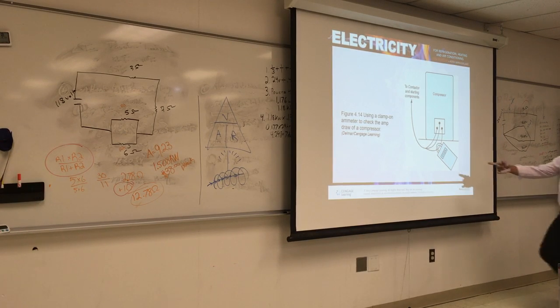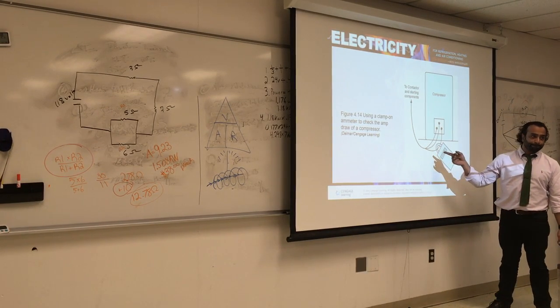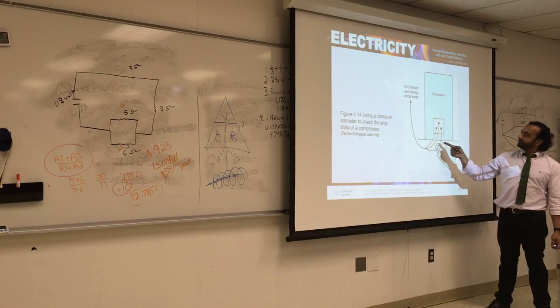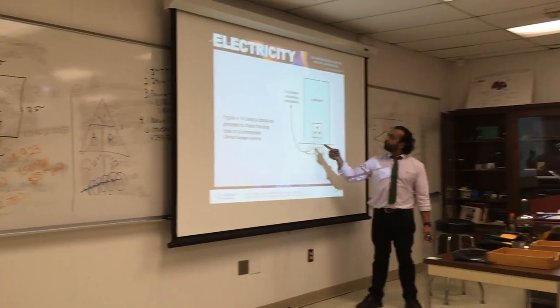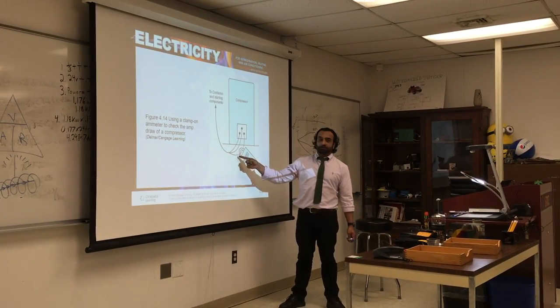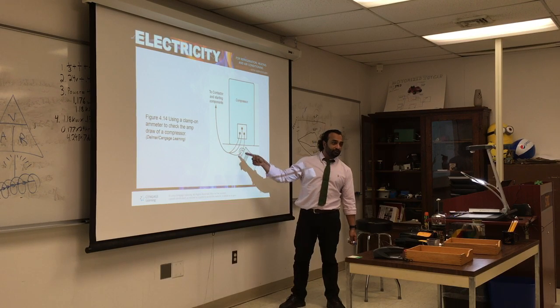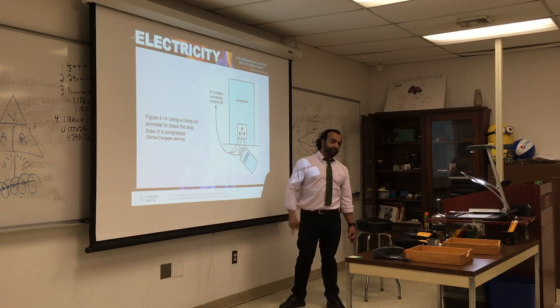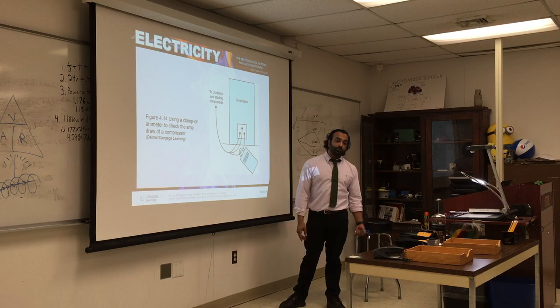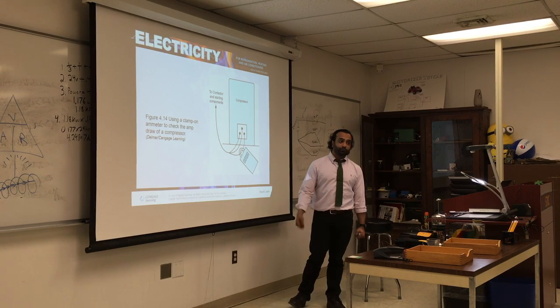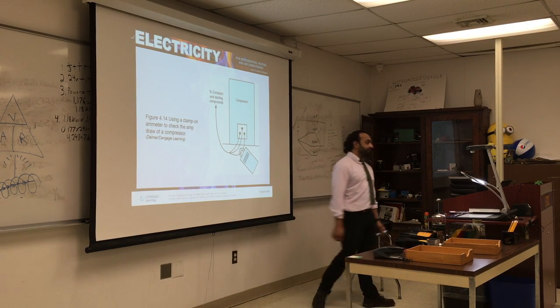So again, if we have a single-phase wire, whether you put your clamp on the hot or neutral, you get some reading. But the equipment has to be on. If you put it on when the equipment is dead or with an open circuit, it's not going to give you any reading.